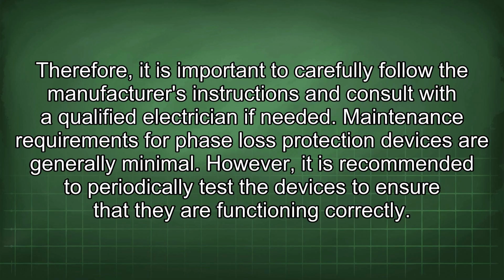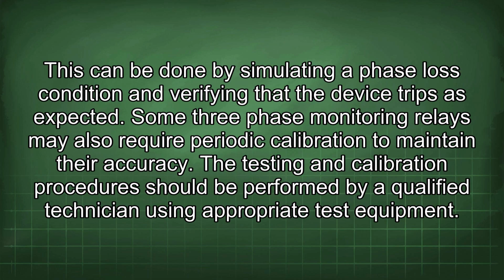Maintenance requirements for phase loss protection devices are generally minimal. However, it is recommended to periodically test the devices to ensure that they are functioning correctly. This can be done by simulating a phase loss condition and verifying that the device trips as expected. Some three-phase monitoring relays may also require periodic calibration to maintain their accuracy. The testing and calibration procedures should be performed by a qualified technician using appropriate test equipment.